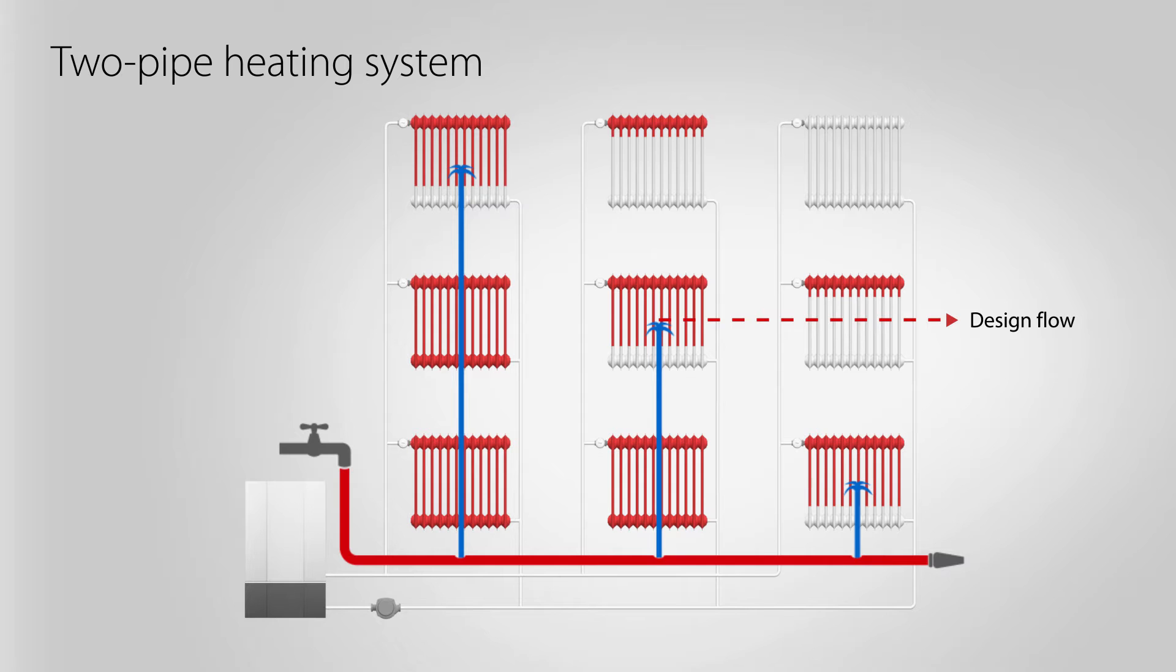In such systems, radiators close to the pump will have pressures that are too high and in turn have too high flows through the radiators. Radiators further away from the pump will experience the opposite, resulting in too low flows through these radiators.